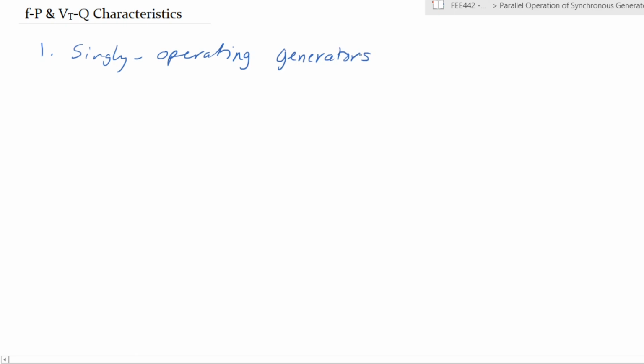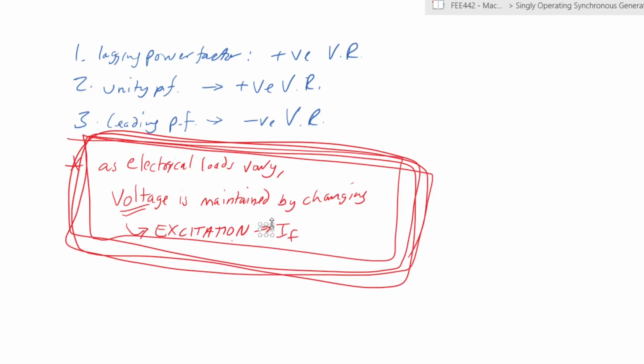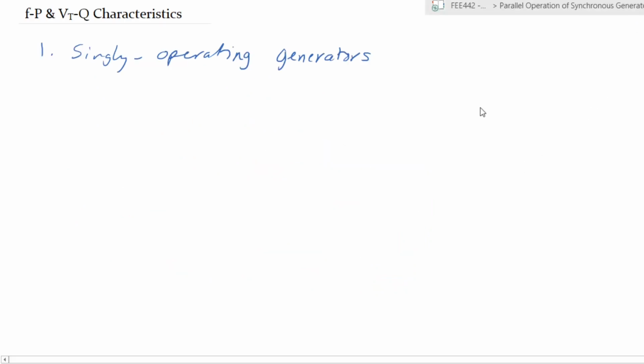Generally, and I will take you back to what we talked about the last lecture we met, you would note that in terms of the voltage supplied by a generator, at the end of that lecture we said that as electrical loads vary, the voltage is maintained by changing excitation. And we said that out of all the things that we will learn within this unit, the most important is that the voltage of a generator is related to the field current or the excitation.